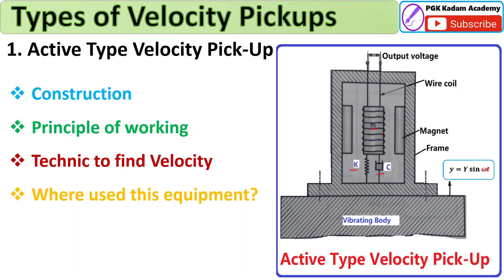The wire coil is mounted on the magnet with mass m. Two surrounding magnets are there, and inside the frame the mass and dashpot are filled. When this instrument is fixed on the vibrating body, the vibrating body has displacement y. When it vibrates, the output voltage changes according to vibration, directly proportional to the relative motion between the coil and magnet.